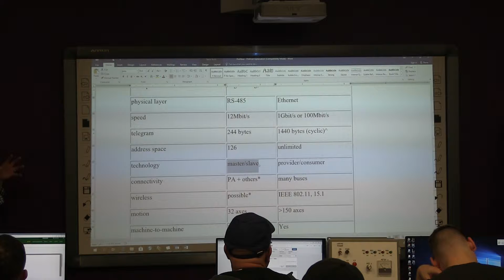This RS-485 stuff, the Profibus, has this master-slave setup. What happens is it slows things down because there's one manager - a PLC, hub, or switch, whatever's managing communications - that sends out tokens to these other devices saying, yep, there's no traffic, it's your turn to talk. So there's one manager in this RS-485 communication.